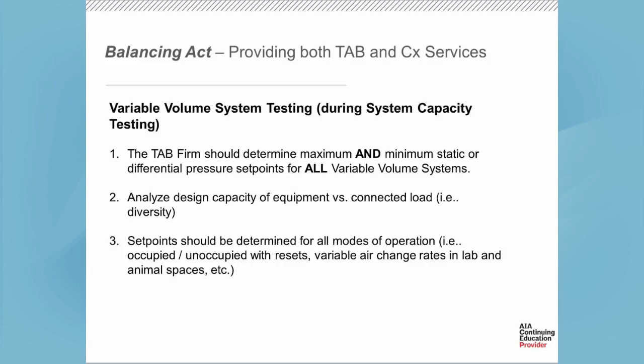Oftentimes we do. You have diversity in systems that's built into the design, and that has to be verified through the TAB process. And then ultimately, there are other set points that need to be put into place in oftentimes more complex control strategies that we're seeing become more mainstream now, like occupied, unoccupied, and static pressure reset scenarios and things like that. And the test and balance firm is the best one to go through and figure out the maximum and minimum range. And then ultimately, the control system can operate within that range. And then as part of the functional testing, you can verify that the system is operating within that range of operations, so that we know we're not going outside of something that hasn't been tested, and we know it's going to be functional.